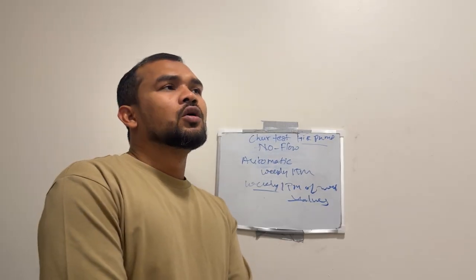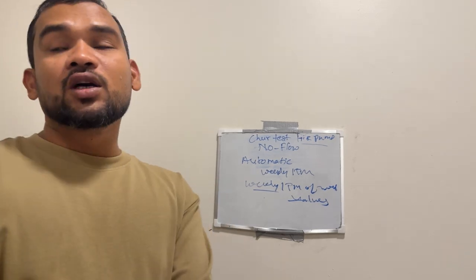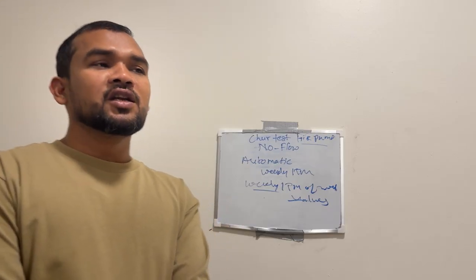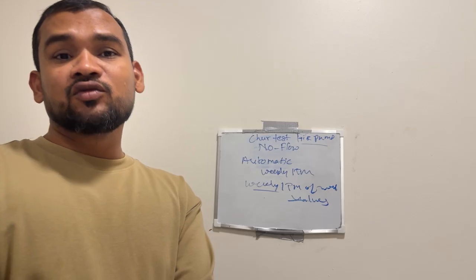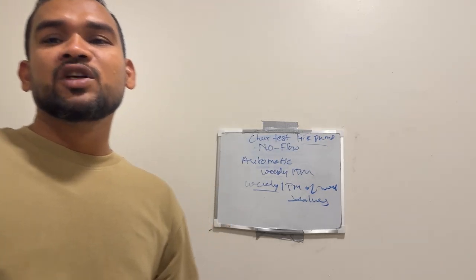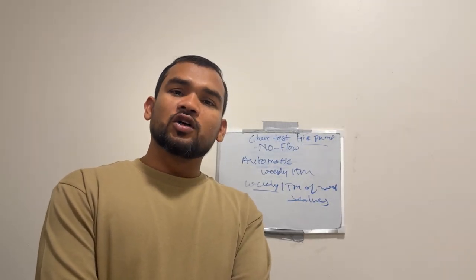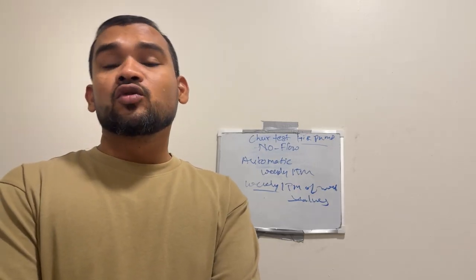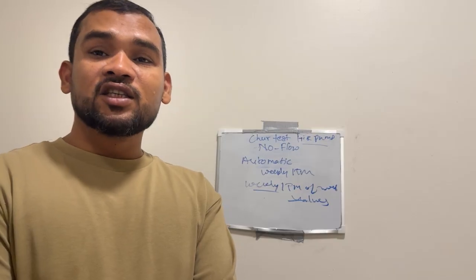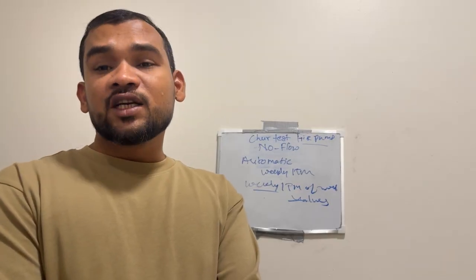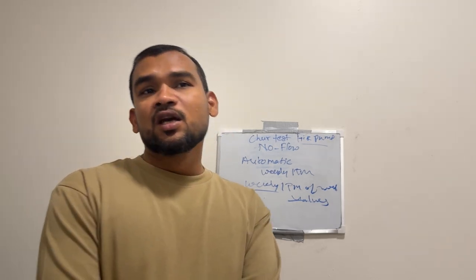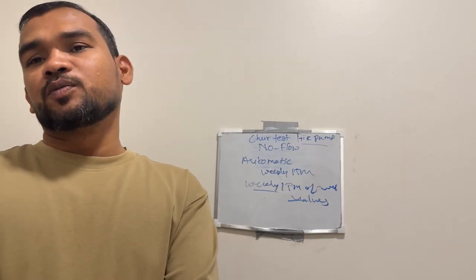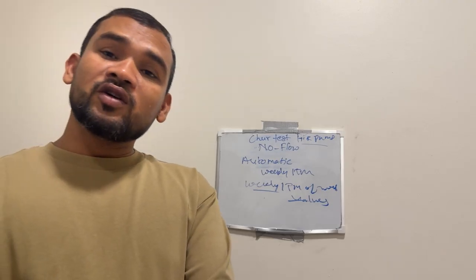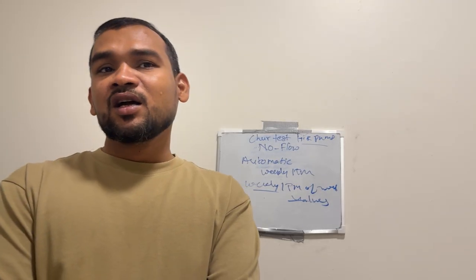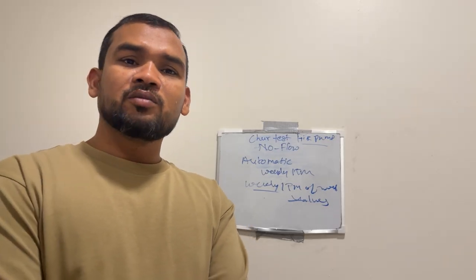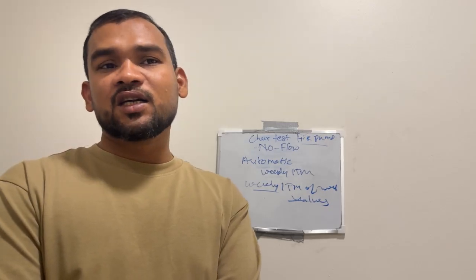The next topic is how we maintain, how to identify required maintenance, who to contact for the maintenance work, and what we have to do to protect the facility in the meantime. For the contact, we have to contact a licensed third-party contractor, inform the AHJ, inform the building owner, and contact the manufacturer or supplier if we require any spare parts. During inspection or testing, if we find any damage, obstruction, corrosion, leaking, painting, or any improper position, we will do the maintenance. This is the maintenance procedure, and we have to contact the qualified personnel, contractor, AHJ, and manufacturer.